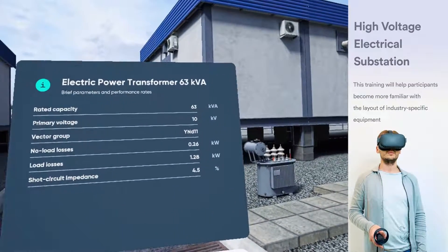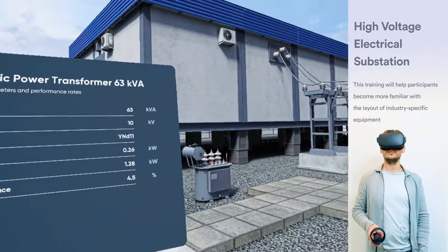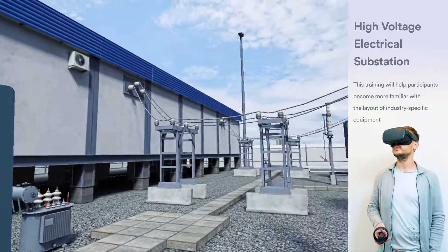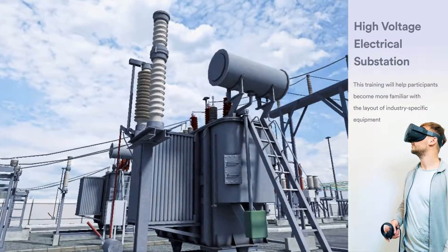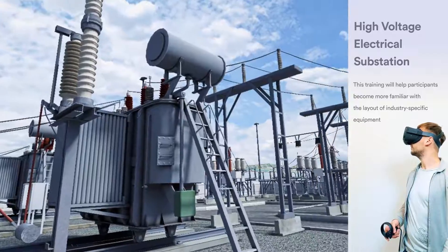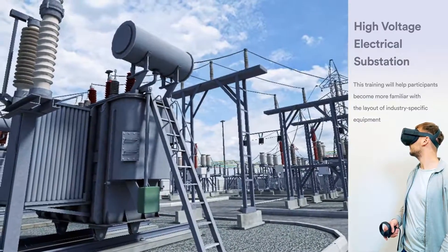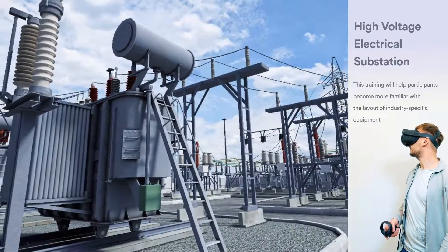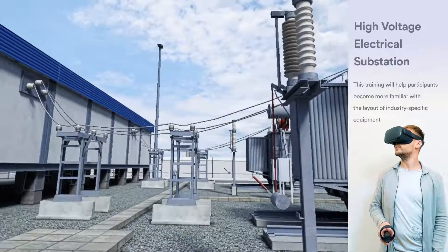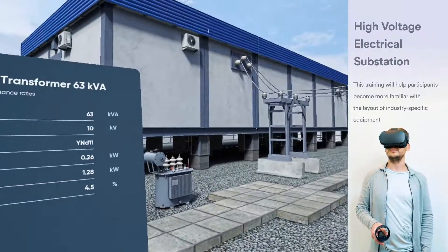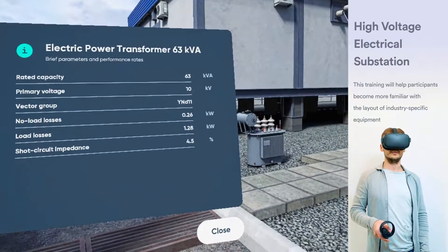To provide a ground path to either an ungrounded Y or a delta-connected system, grounding transformers are part of an earthing system of the network. They let three-phase systems accommodate phase-to-neutral loads by providing a return path for current to a neutral.